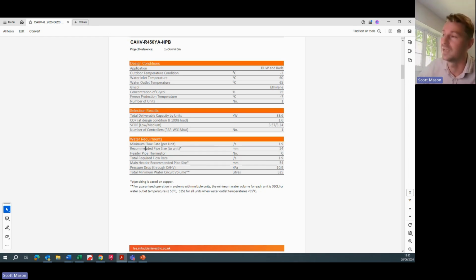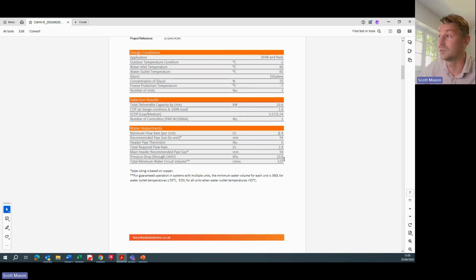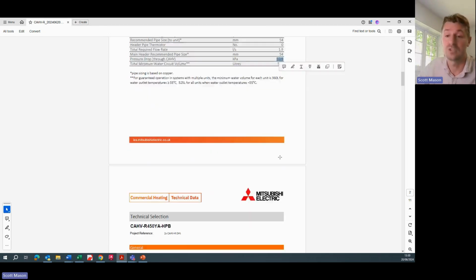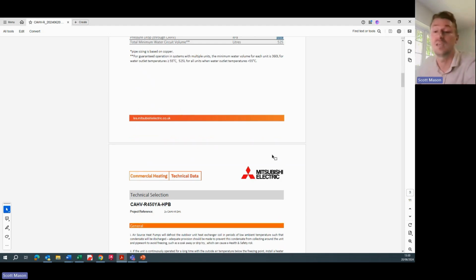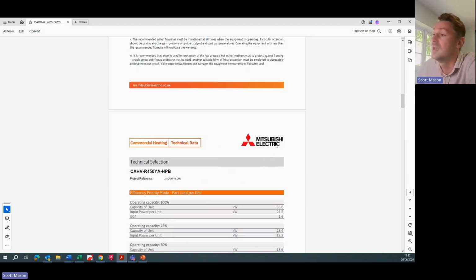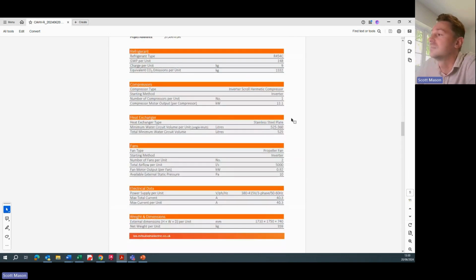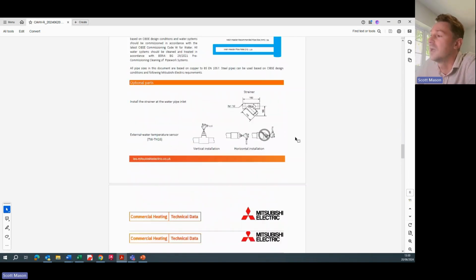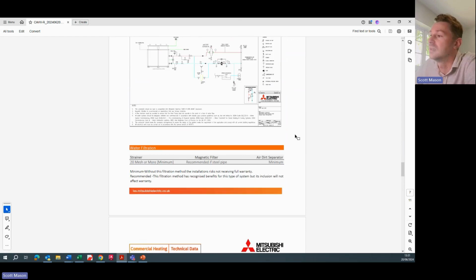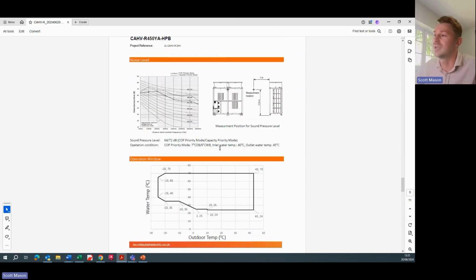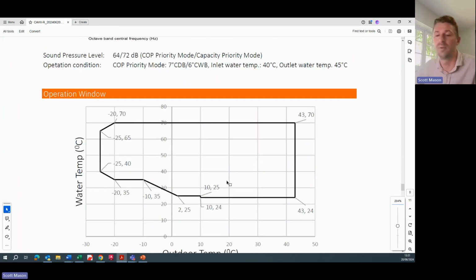It's a different thing. So it's worth considering that flow rate is going to have an impact on your pipe size, and the pipe size is going to have an impact on your pressure drop. The pressure drop of the unit is also going to be prescribed so that you can make sure the pumps we use are going to circulate appropriately. It gives you a load of nice tech clauses, things you would expect to see, and it will also give you some indicative drawings and, crucially, that all-important operating window.